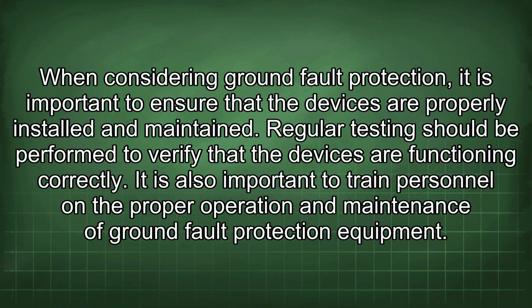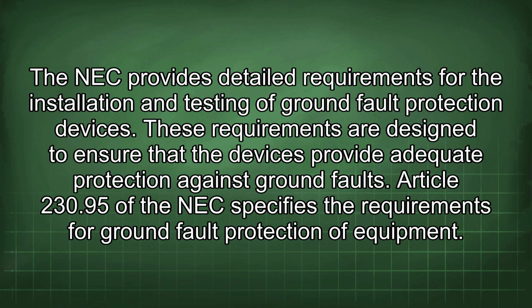When considering ground fault protection, it is important to ensure that the devices are properly installed and maintained. Regular testing should be performed to verify that the devices are functioning correctly. It is also important to train personnel on the proper operation and maintenance of ground fault protection equipment. The NEC provides detailed requirements for the installation and testing of ground fault protection devices. These requirements are designed to ensure that the devices provide adequate protection against ground faults.